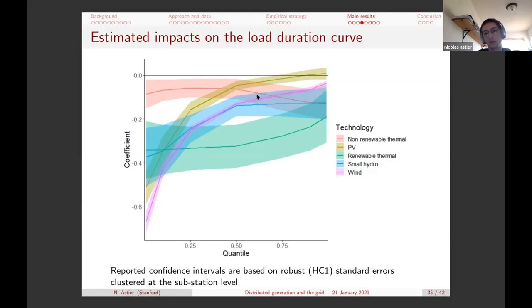And what was more surprising was perhaps for wind, because wind generation is higher during the winter. So we kind of hoped that it would have a higher impact on peak load. It does have a statistically significant impact. So it does help a little bit, decreasing the need for capacity investment. But it's a very small decrease. So a 1 megawatt increase will, on average, yield a 0.04 decrease in the 99th quantile. So that was somewhat disappointing.